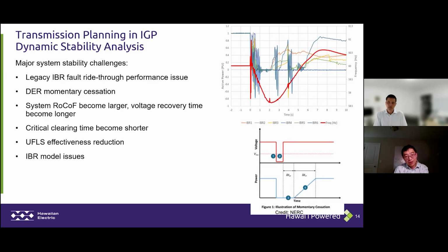Right now, our commission approved a project for us to transition the Oahu load shedding system from a static scheme to a dynamic scheme. But basically, we will need more load in this load shedding program to help maintain its effectiveness. The last thing is about the IBR model issue. I'll talk about that in later slides, but we do see there's a chance that an IBR gets commissioned in a system, and during the commissioning, the folks doing the commissioning are totally not aware of the IBR study settings and just use default OEM settings. And apparently, our interconnection study finds that most of the time the default IBR settings won't work. We need something special. Next slide, please.